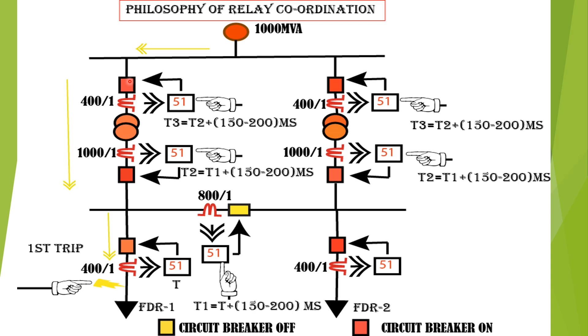This is how relay coordination is done in a particular substation. The bus coupler overcurrent relay acts as a backup for the feeder overcurrent relay. The LV side overcurrent relay acts as backup for both feeder and bus coupler overcurrent relays. And the HV side overcurrent relay acts as backup for all three overcurrent relays. This is the basic philosophy of relay coordination in a substation.